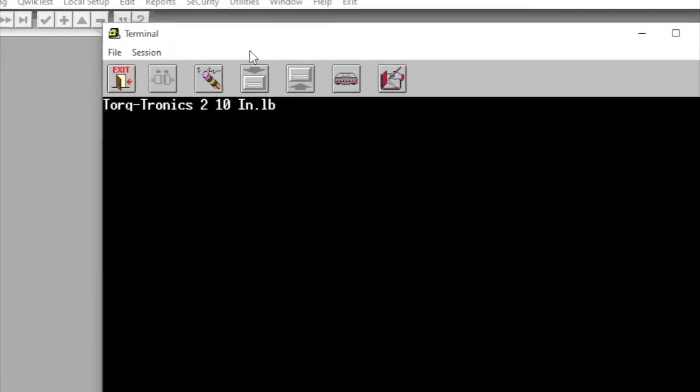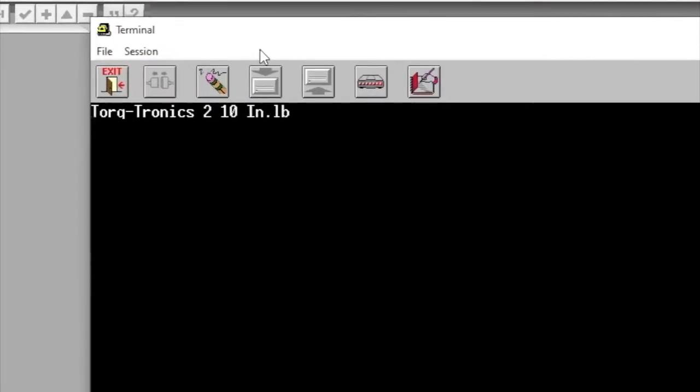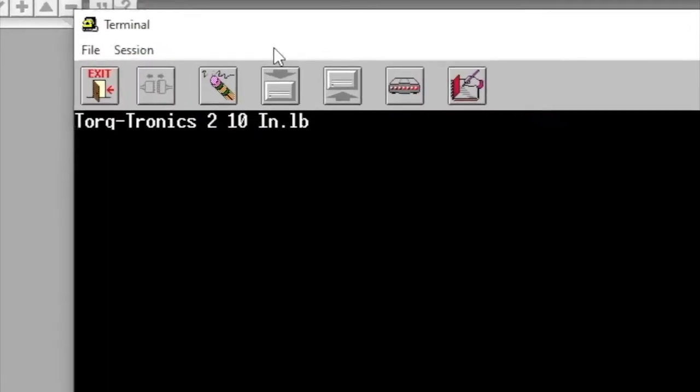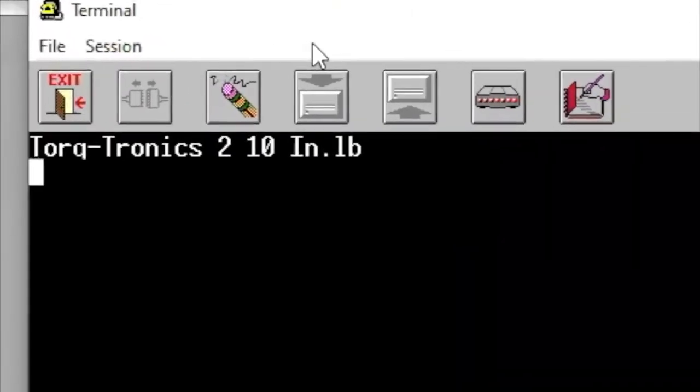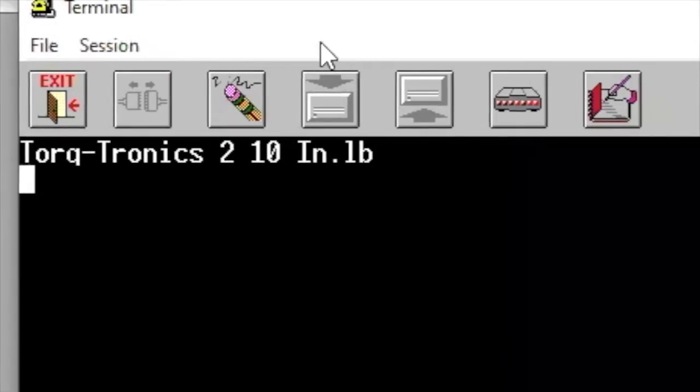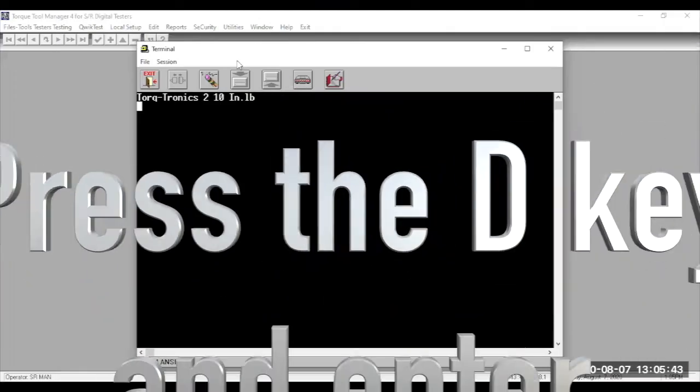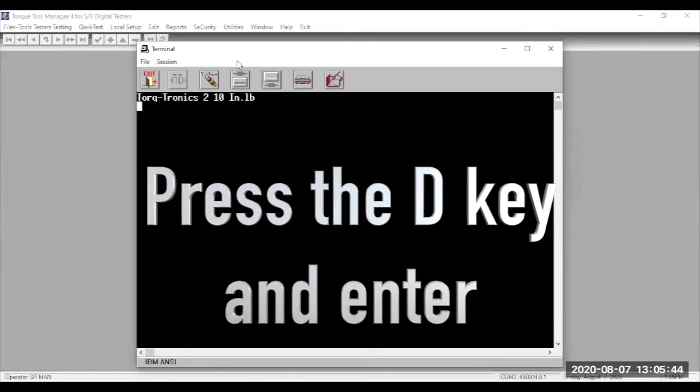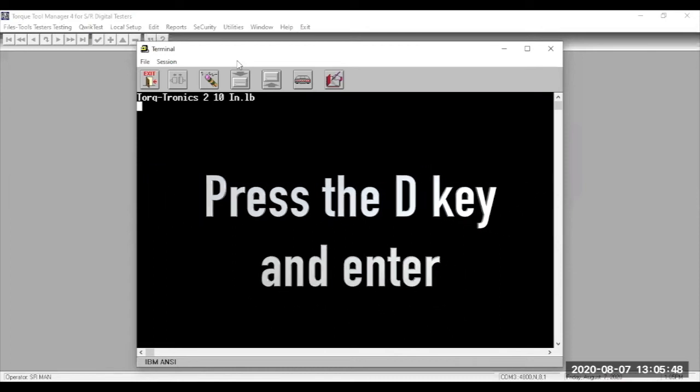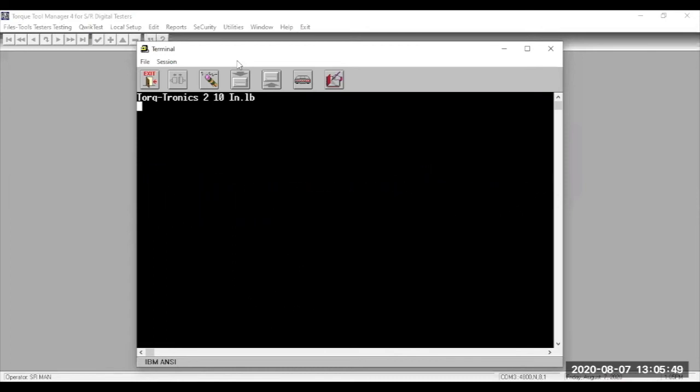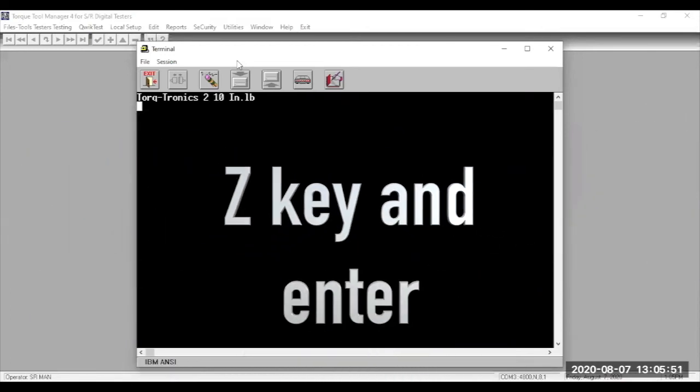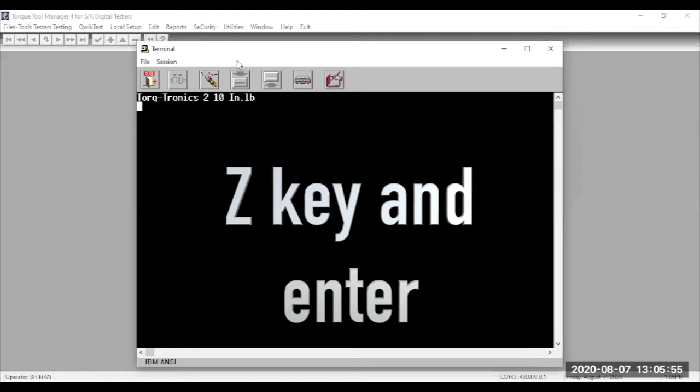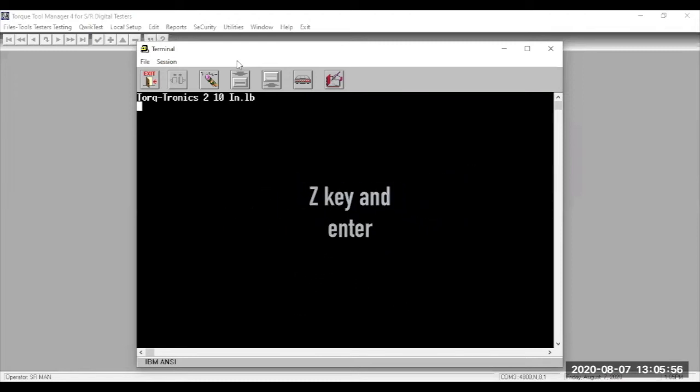So, now you're ready to reset the overload flag. Press the D key and press Enter. This initiates the diagnostic program. Press the Z key and then press Enter. This resets the flag. At this point, the pulsing red LED should stop.